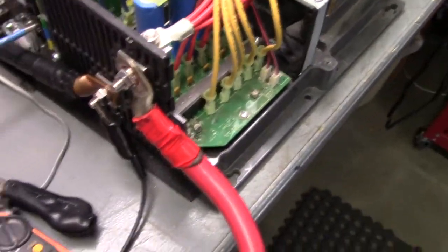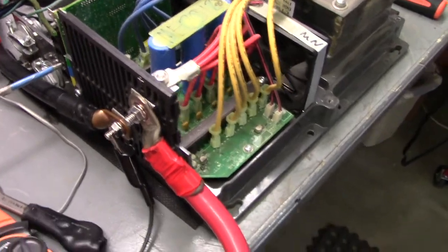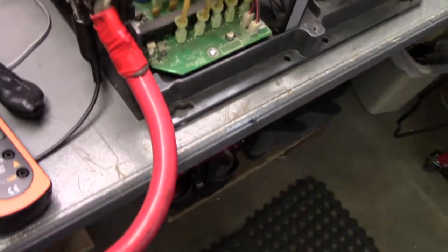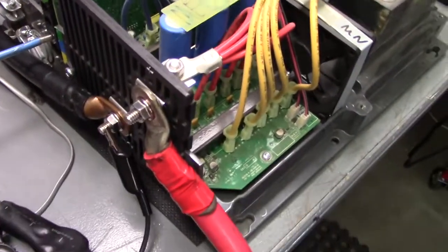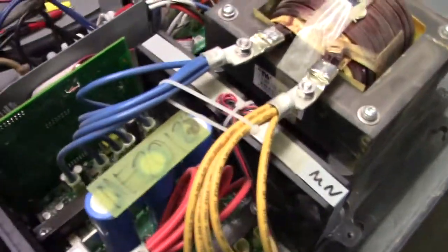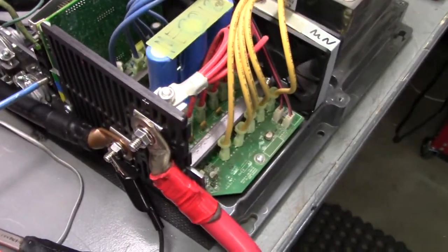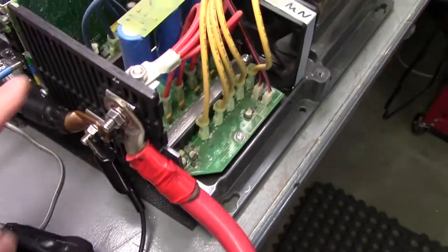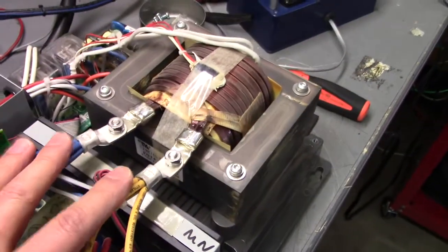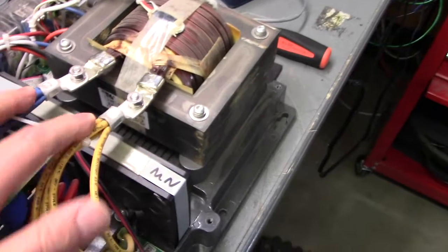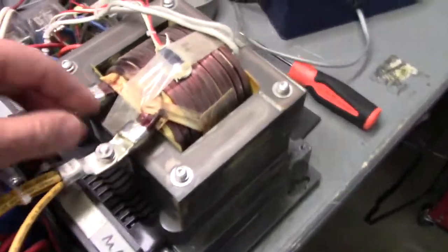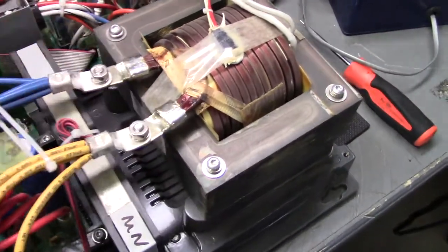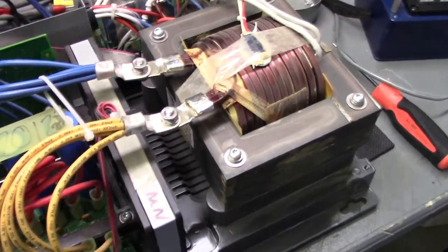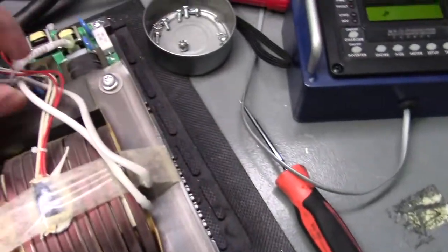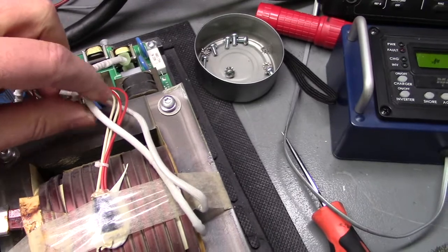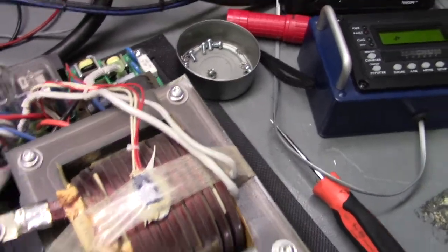The current coming into these units can get quite high, so we have very large wires on our test bench. I forget what the continuous rating on this one is, but you have to be able to support a couple hundred amps coming in, and it actually will pump 200 to 300 amps into the primary of this transformer. You can see how heavy these wires are because there's a lot of current. And then your output, since it's up at 120 volts, you have thinner wires, lower current.